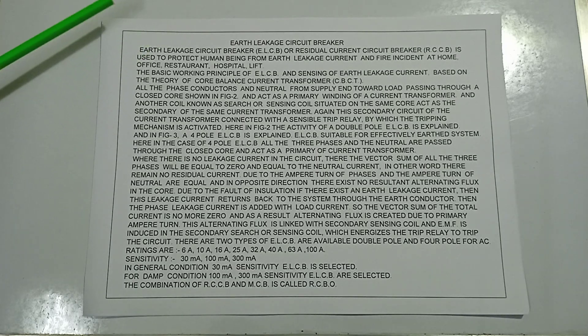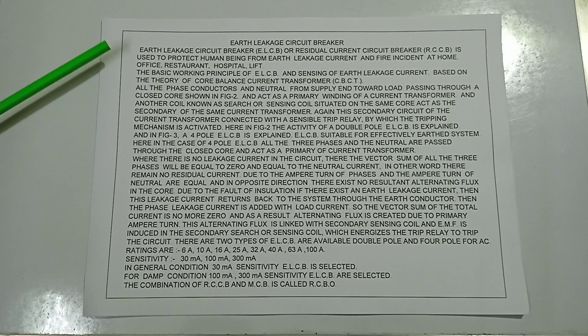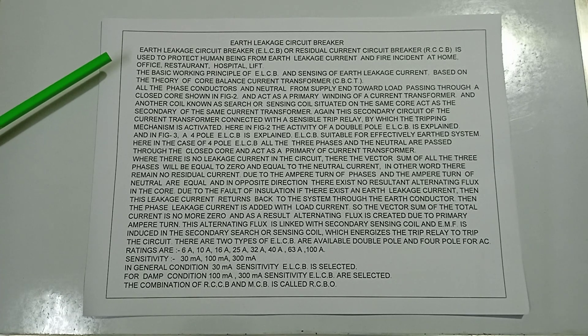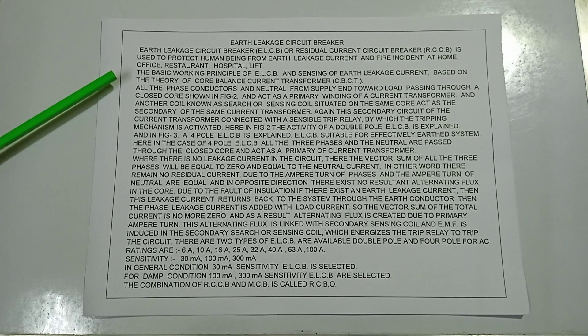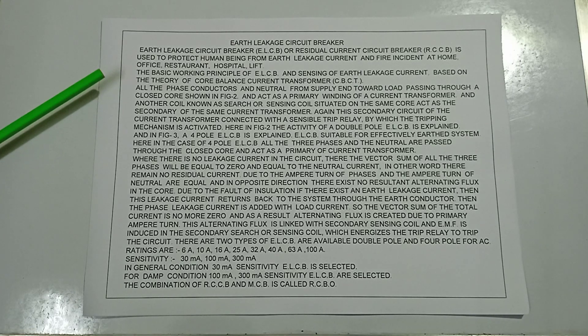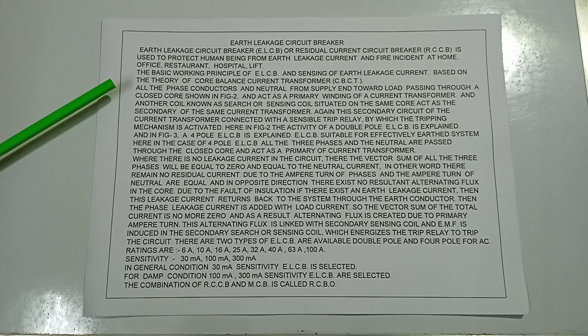Earth leakage circuit breaker (ELCB), also called residual current circuit breaker (RCCB), is used to protect human beings from earth leakage current and fire incidents at homes, offices, restaurants, and hospitals. The basic working principle of ELCB involves sensing of earth leakage current based on the theory of the core balance current transformer (CBCT).